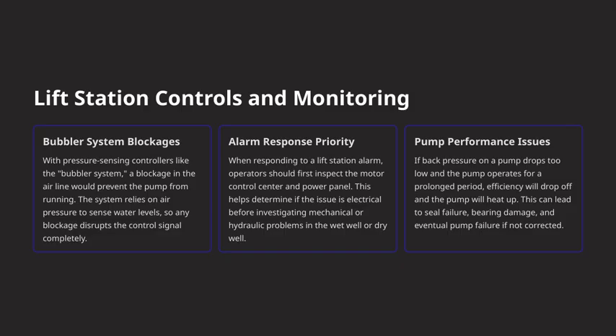Now, moving on to alarm response priority. When an alarm sounds at a lift station, the first step for operators should always be to inspect the motor control center and power panel. This helps us quickly determine if the problem is electrical, like a power issue, before diving into mechanical or hydraulic problems in the wet well or dry well. Addressing electrical issues first can save us time and prevent unnecessary downtime.